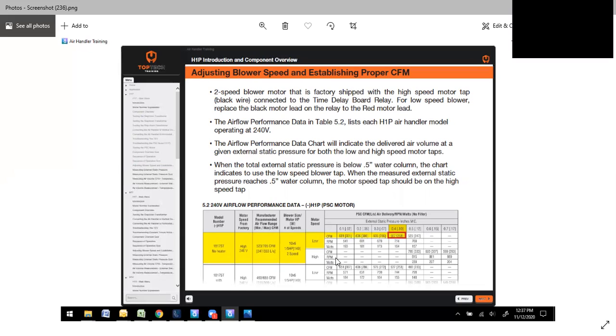And if we go into high speed here, at a given CFM, at a higher static, we need a higher speed. So if we're at 0.7 and we're in high speed, we're pushing about 599. It gets different when you get into the ECMs and the constant torques, but it is important that you read your static pressure and understand that. At that point, you can set your blower speeds accordingly.